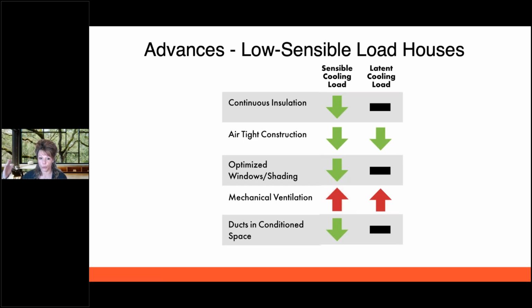The challenge is we're going to have to do that with mechanical ventilation, which you can see can increase our sensible load and our latent load. Now, ducts in conditioned spaces is going to drive down that cooling load. And I would also say that it's going to drive up our latent cooling load, because as soon as you put ducts in a conditioned space, the AC will run less, because we're not losing that conditioned air into an unconditioned attic, causing the air conditioner to run longer, which actually helped remove more moisture.